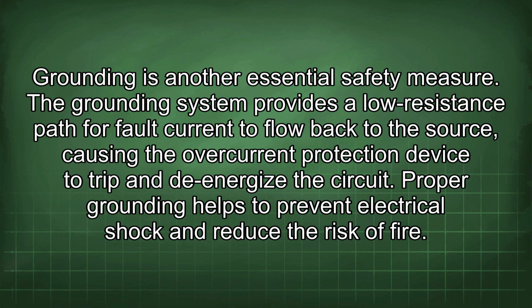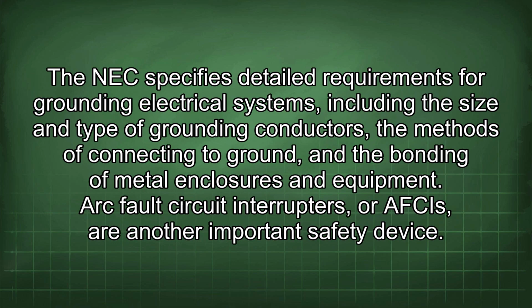Grounding is another essential safety measure. The grounding system provides a low resistance path for fault current to flow back to the source, causing the overcurrent protection device to trip and de-energize the circuit. Proper grounding helps to prevent electrical shock and reduce the risk of fire. The NEC specifies detailed requirements for grounding electrical systems, including the size and type of grounding conductors, the methods of connecting to ground, and the bonding of metal enclosures and equipment.